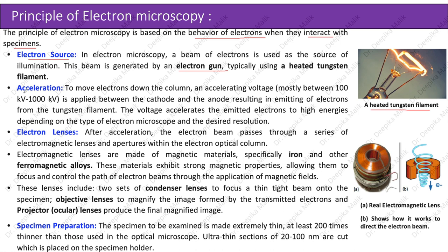Acceleration: to move electrons down the column, an accelerating voltage, mostly between 100 kV to 1000 kV, is applied between the cathode and the anode, resulting in emitting of electrons from the tungsten filament. The voltage accelerates the emitted electrons to high energies depending on the type of electron microscope and the desired resolution.